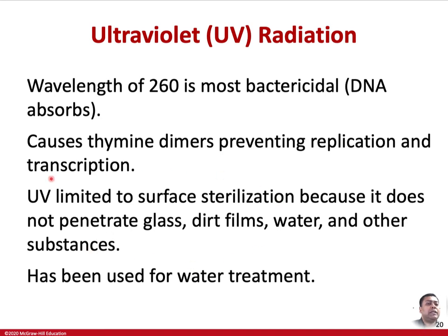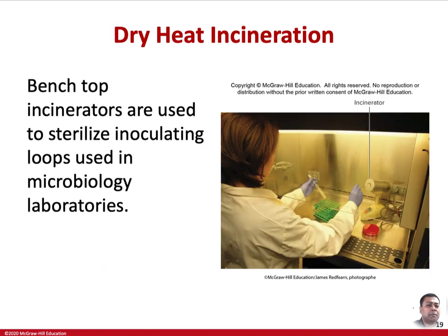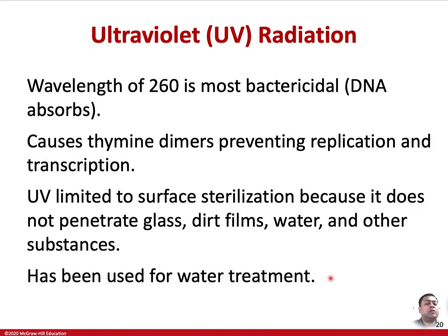So these are routinely used to sterilize, for example, biosafety cabinets or laminar flow cabinets that we just saw. For example, right here, in the front there is acrylic or glass, which is not UV penetrant, and you just lower down that glass shield to completely close that biosafety cabinet, turn off the light and turn on the UV light inside, and you can turn it on for about 30 minutes to 45 minutes, and the surface will be sterilized after that. So this is how it is used. Routinely used also in the operating chamber or operation theater as well.